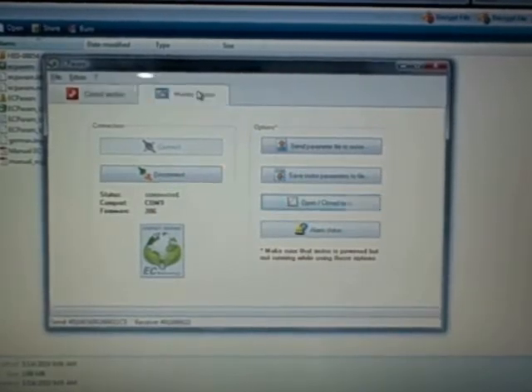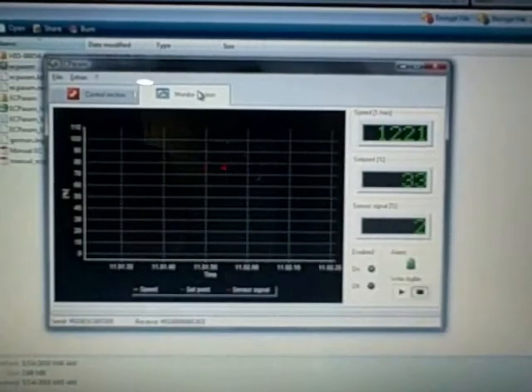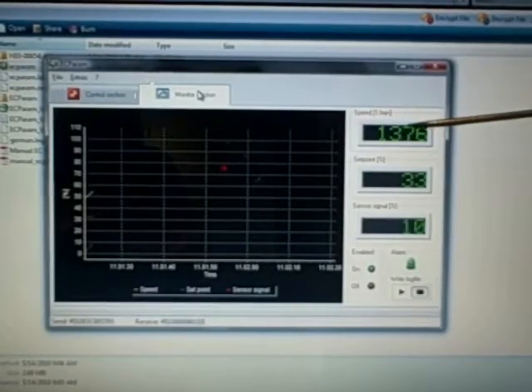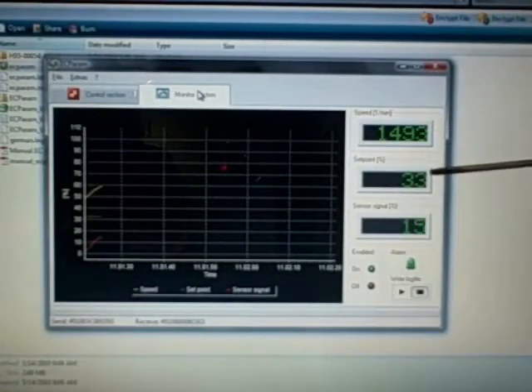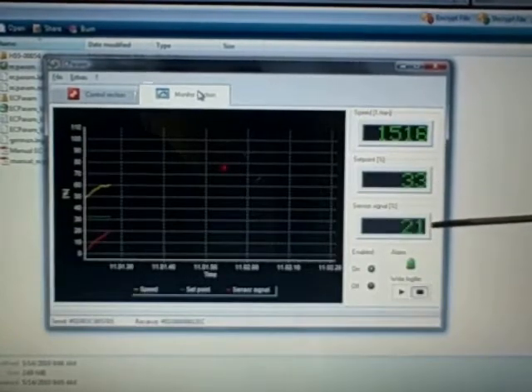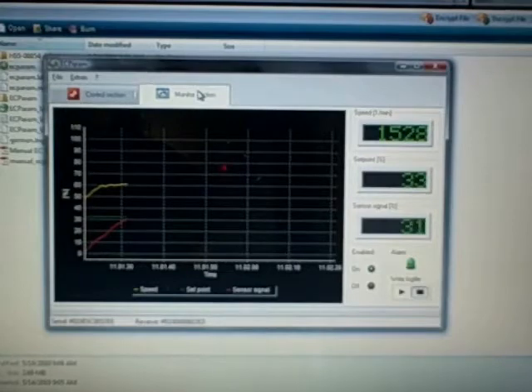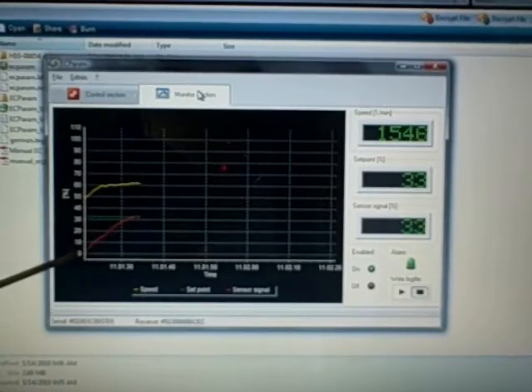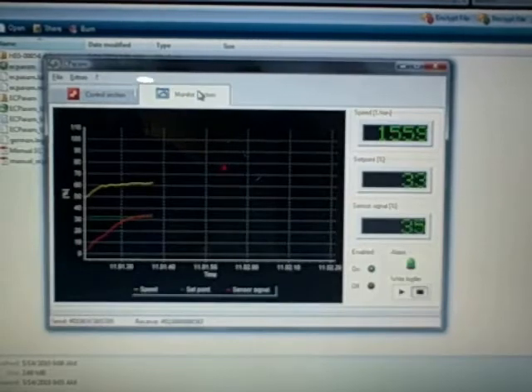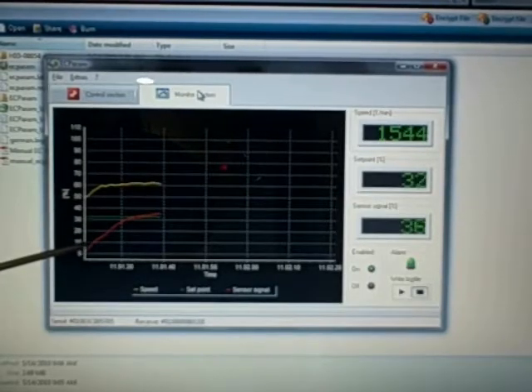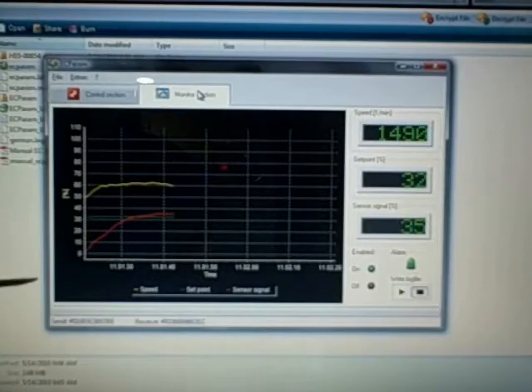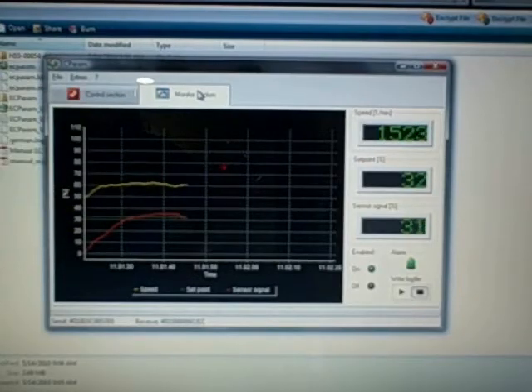Now we'll go back to the monitor section here. Now you've got three sets of controls. Still got your speed. You've got your set point, which right now we're running about 33%, and you've got your signal set point, which being your differential pressure switch in our case here. And that's indicated here by the red line. Now the damper on our setup right now is fully open. So what you're reading is the pressure difference between the inlet area and the inlet cone. So everything balances out. Everything will get to where it needs to be.